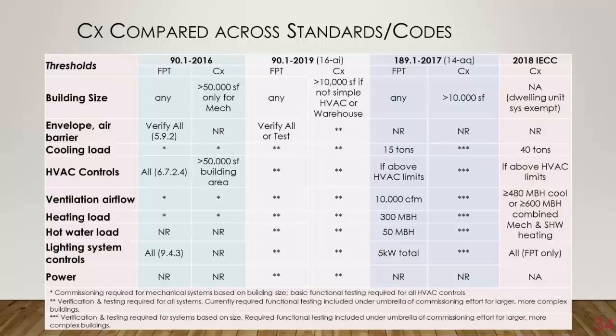In 189.1, their cutoffs are a little bit different. They actually don't require functional performance testing in all buildings. They have some lower limits as far as system size that 90.1 doesn't have. We say, hey, you're supposed to check it. Even a programmable thermostat, someone should take a look and make sure that's set up correctly, even in a small building. So there's some minimum system sizes as far as hot water load, airflow, and heating load capacity that happen in 189.1. And then as far as commissioning, they require it basically once you get over that 10,000 square foot limit and you've already got these requirements on the performance testing.